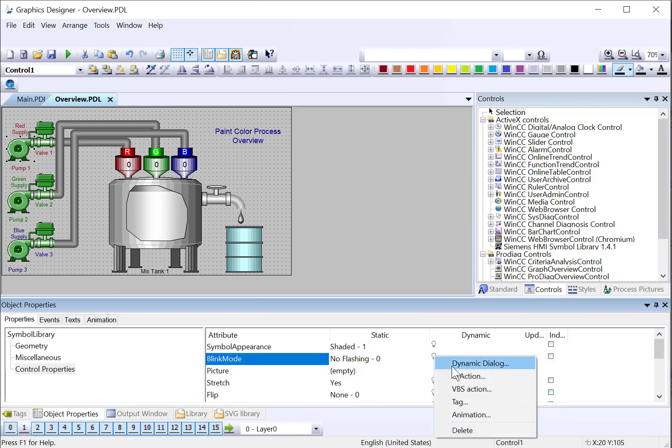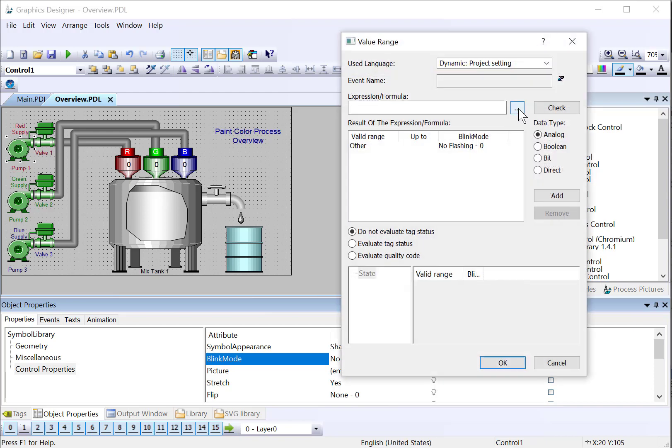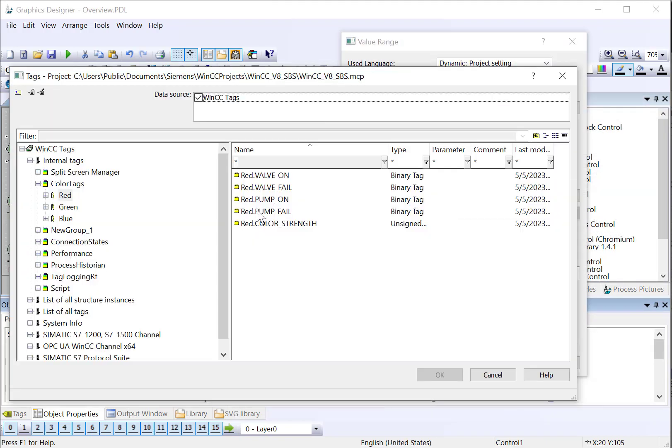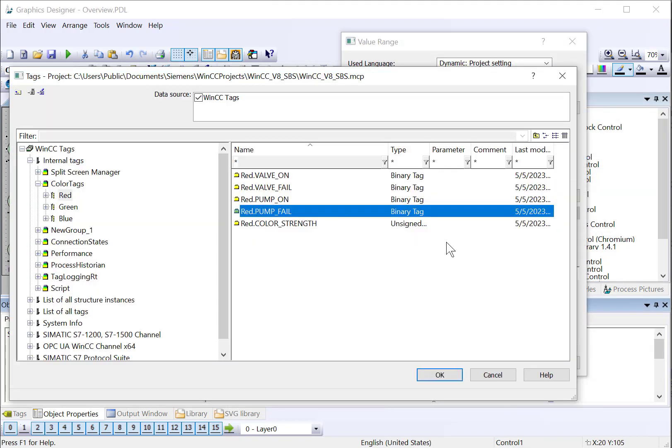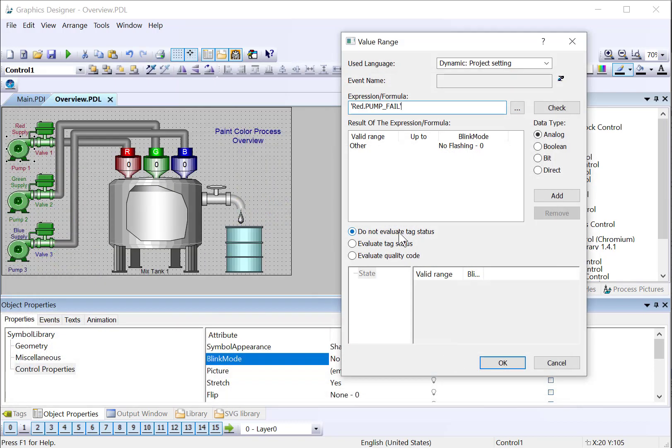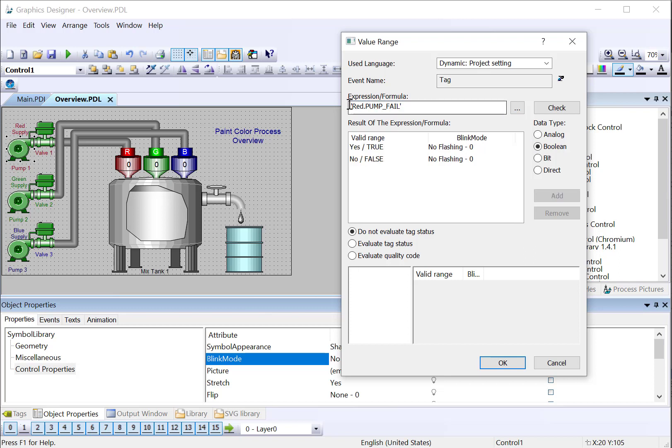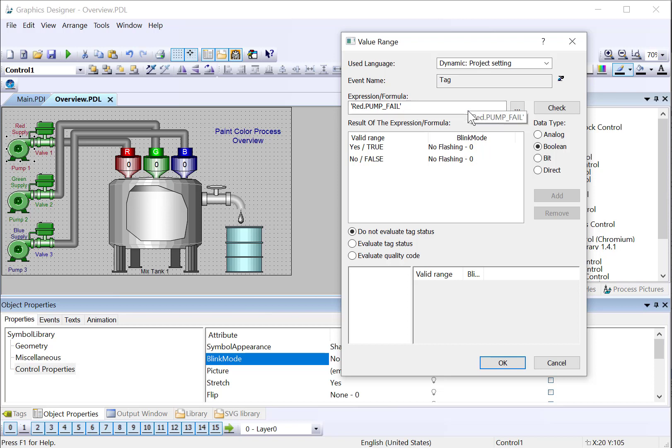And we've set the blink color to this yellow. So I'll right-click and choose dynamic dialog. I'm going to choose my red pump fail tag for this. Dynamic dialog is just a tool that will evaluate an expression, and then you can choose the appropriate data type for that expression, and it will set the property. So if we just put the tag name, this will resolve to the actual value of this tag, which is going to be true or false.